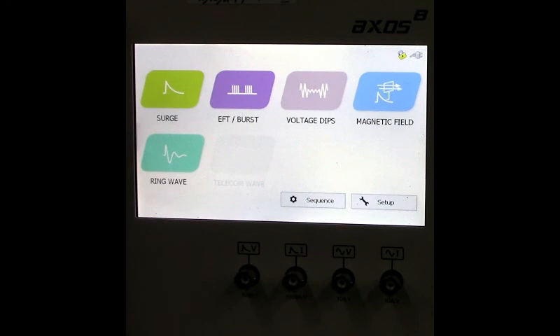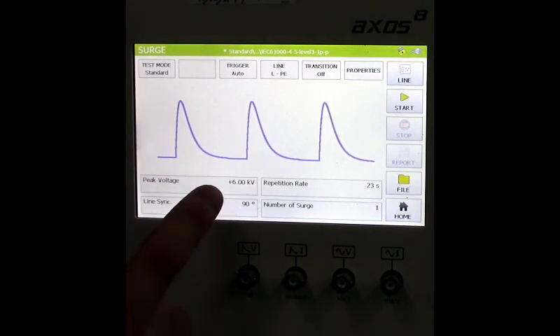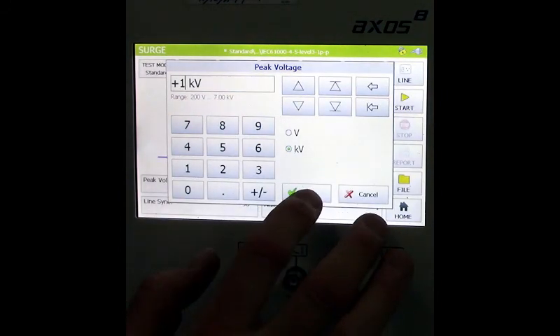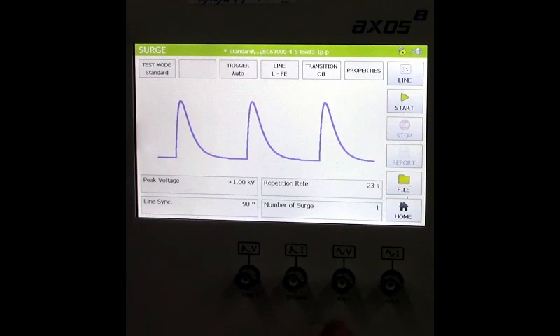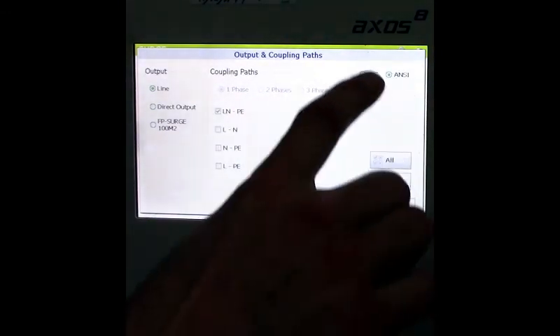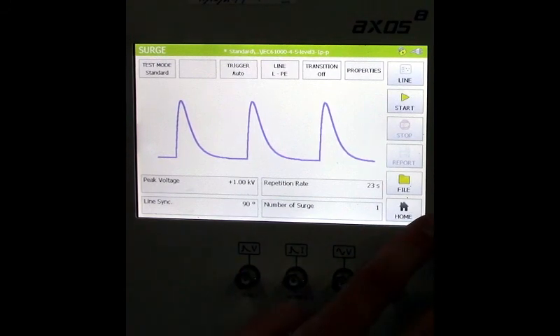Here's the home screen for the AXOS 8. You'll see surge, EFT, burst, voltage dips, magnetic field, and ring wave. We're going to focus on surge and ring wave. For surge, you can easily adjust parameters — for example, changing the peak voltage from 6 kV to 1 kV: hit the back button, type 1 kV, select OK, and it saves on screen. You can also toggle between IEC and ANSI coupling modes, as different testing standards require different coupling methods.